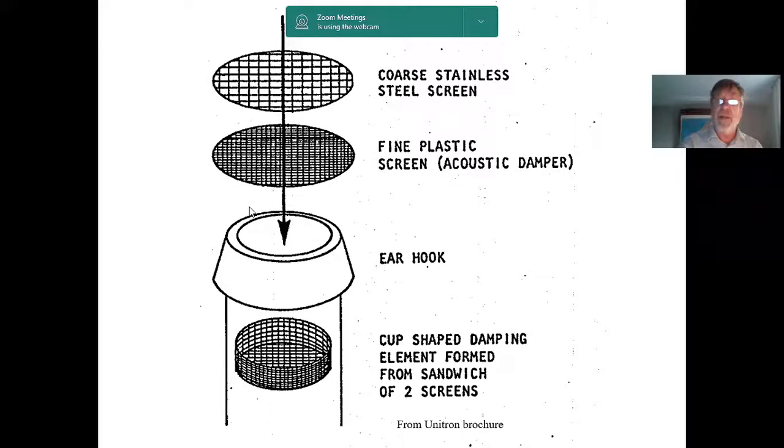Good. Transducers. Hearing aids are two transducers, a mic and a receiver. And think of the receiver as the speaker. Okay? So filters are right beyond the speaker, and they smooth the frequency response. And they do that by providing a tiny little screen, and that's stuck in the ear hook. Okay? I'll show you another example of a filter.